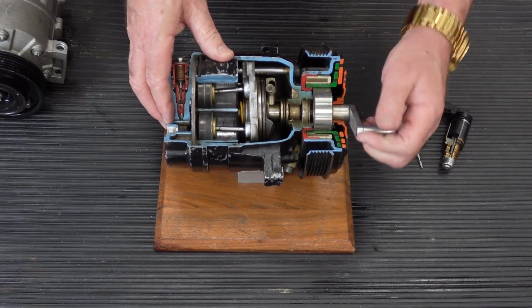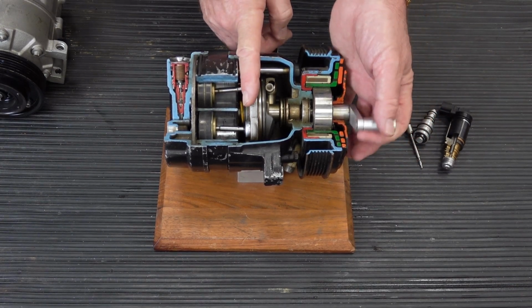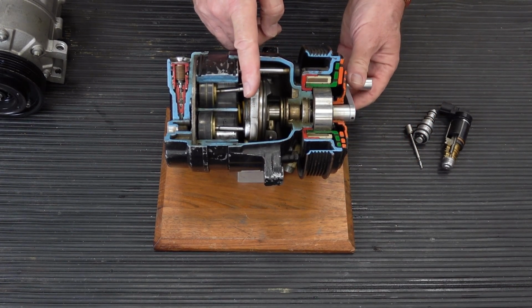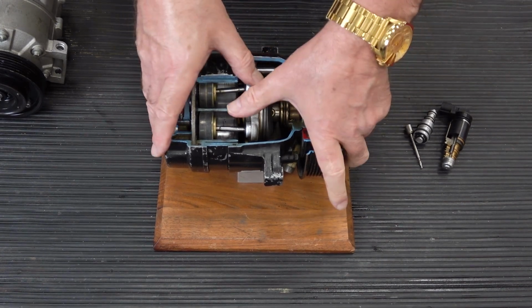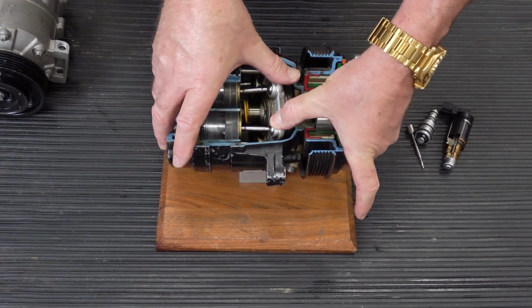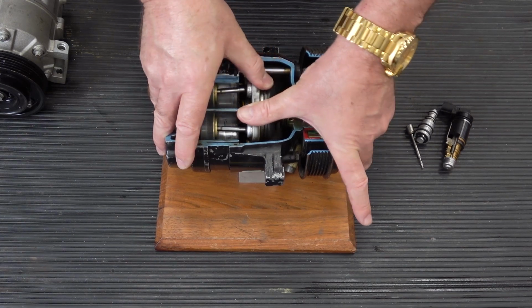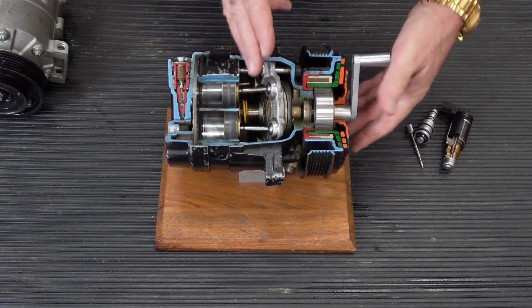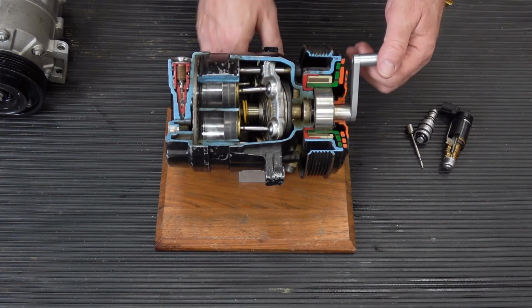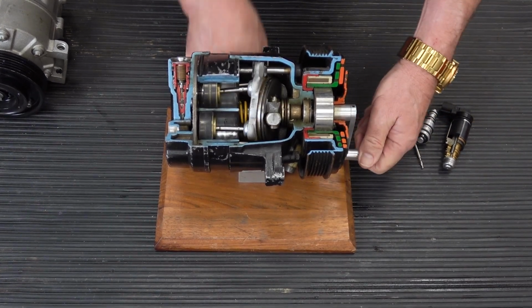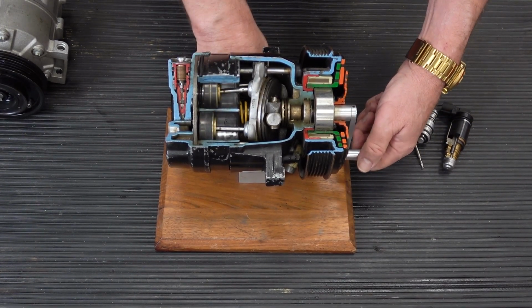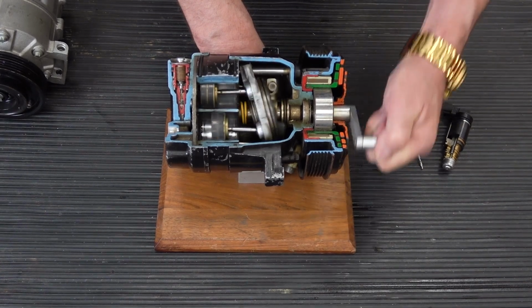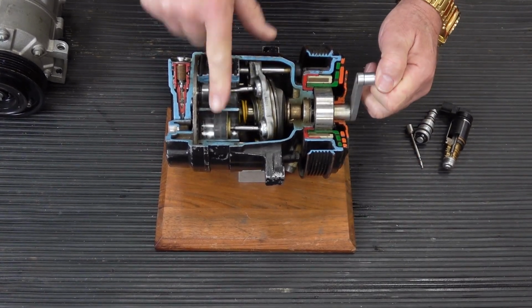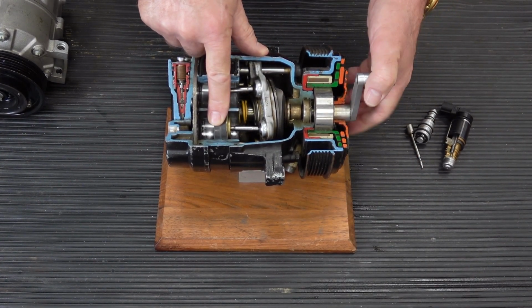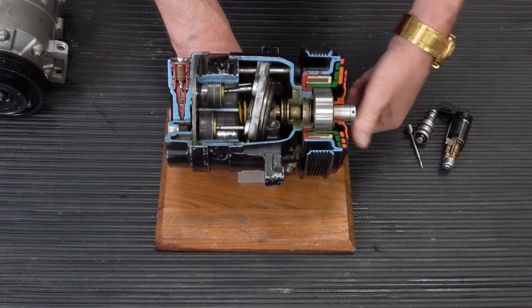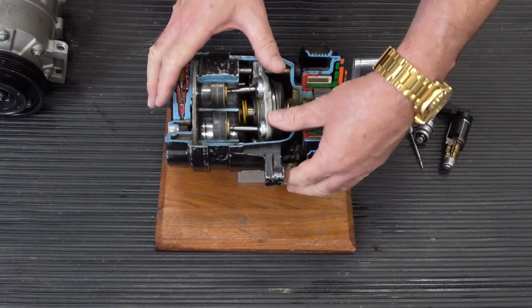So what I want you to see here, inside this compressor, there's a wobble plate. Later models, we call it a swash plate. And you can see this wobble plate, I can change the angle of that wobble plate or that swash plate. And so you see, I've got it at a very steep angle here to the crankshaft. Now, when I turn the compressor, do you see that the pistons are traveling back and forth quite a ways? In other words, the pistons have quite a long stroke. They're at maximum stroke. Well, watch what happens if I change the angle of that swash plate.